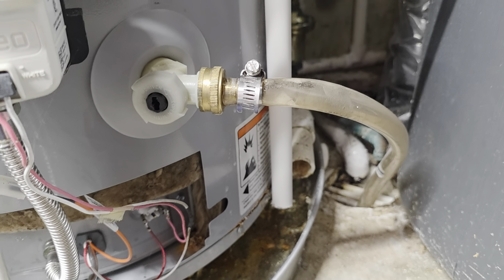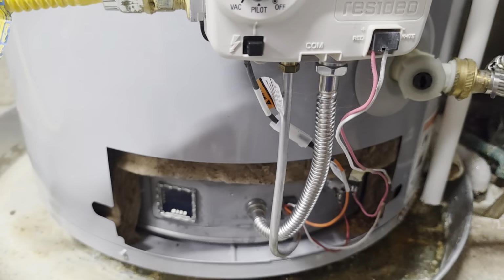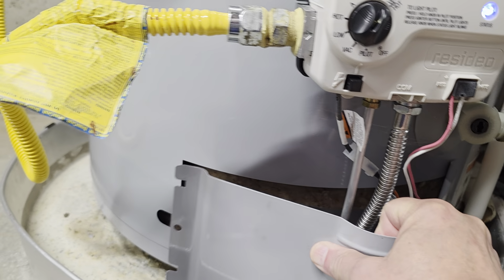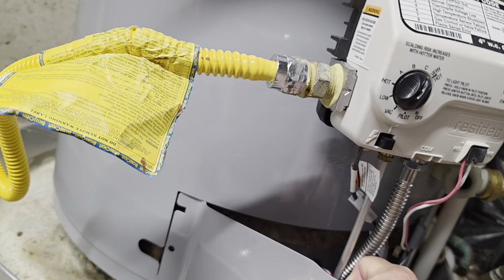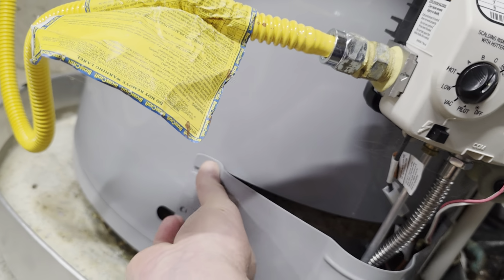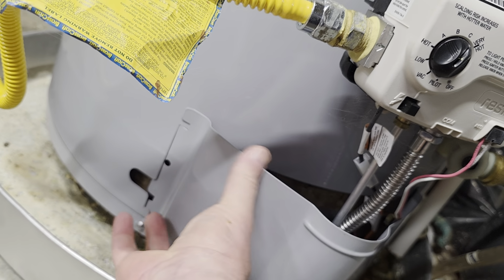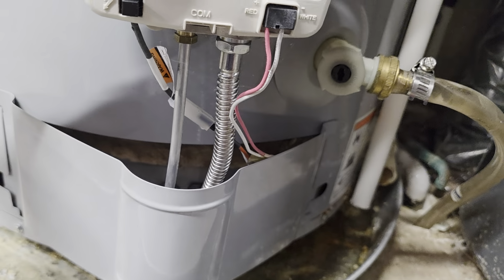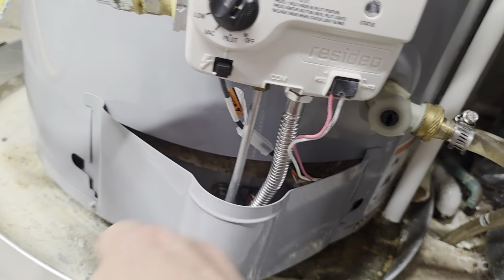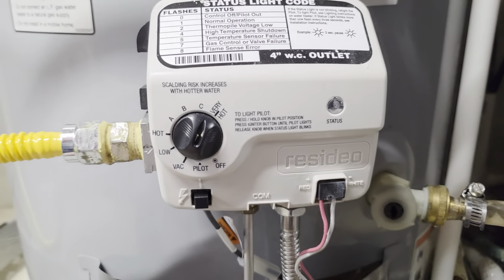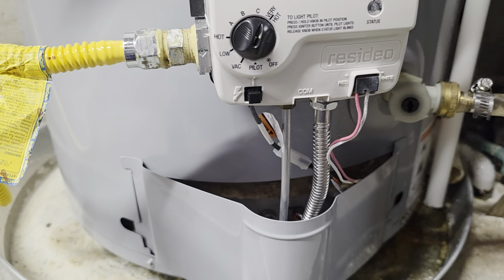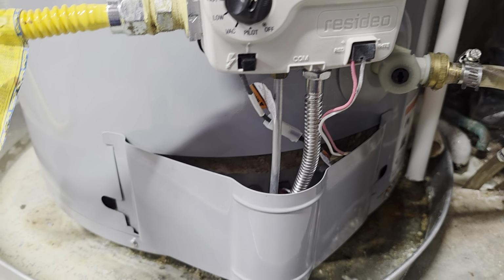Now, as a tip, understand that you don't have to open up your channel section here like I did. You can just leave that part closed and not worry about that component per se. Sometimes it can be a little bit of a pain to put back on, but a lot of people will do that. I do that just to check to see if there's moisture in the bottom, because that means you have condensation on the outside of the tank and it's dripping down, and that can cause the tank to rupture from the outside in versus the inside out. It does happen.